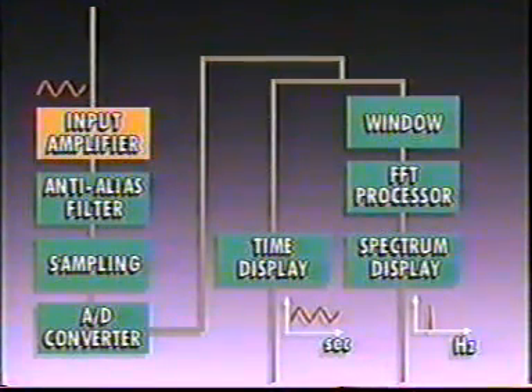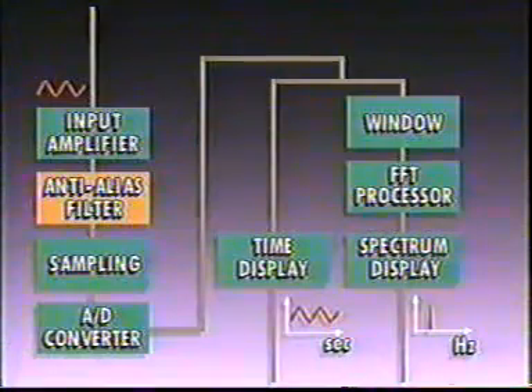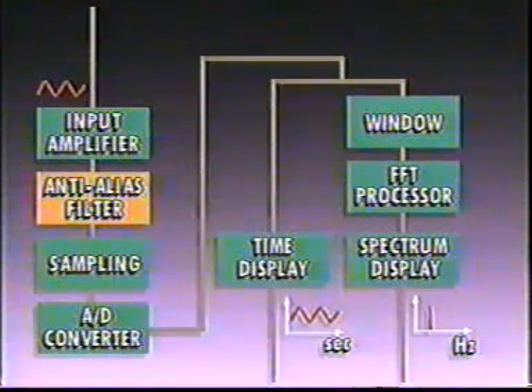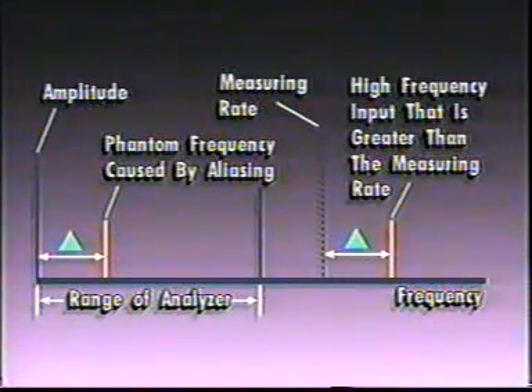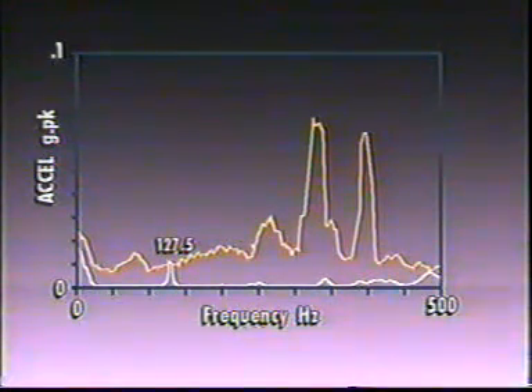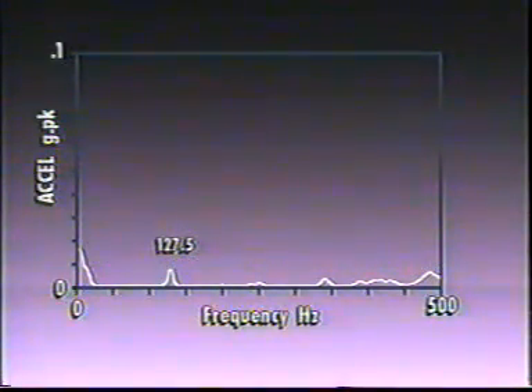The FFT analyzer has an input amplifier section to boost the millivolt signal from the sensor to a usable voltage for the rest of the system. Next, the signal passes through a low-pass filter called an anti-alias filter. Aliasing is a false signal caused by digital sampling of a high-frequency signal. The result is a false low-frequency component. If there are actual low-frequency signals present, the false signal will be added to the true signal, and erroneous amplitudes will result. The anti-aliasing filter removes the false low-frequency component from the high-frequency signal.